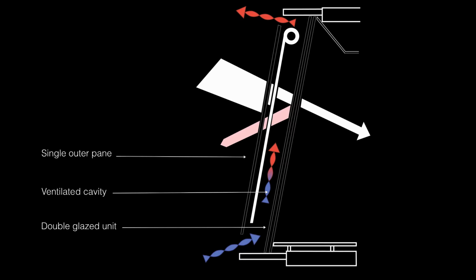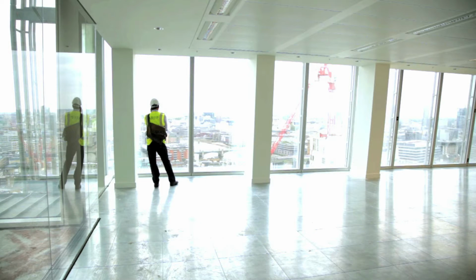This traps the heat from the sun in the external cavity, which is then ventilated outside, minimising mechanical cooling loads and giving an associated efficiency in plant and riser space - a key consideration in tall buildings where space is at such a premium. As a result of the deployable blind, the glazing itself doesn't need to perform a significant solar control function, allowing it to be more transparent.